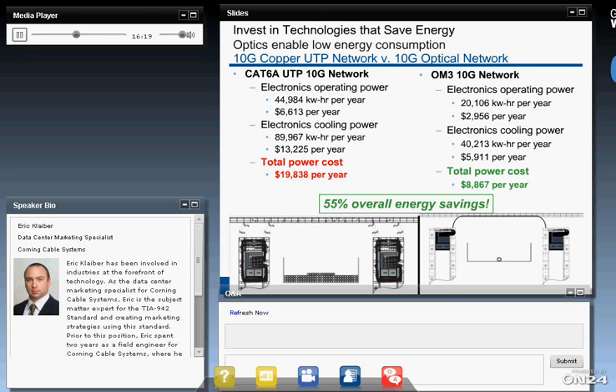You can see just because of that wattage difference per port, there is a substantial savings going from copper to fiber. So copper is more expensive, fiber is less expensive. This is a yearly savings. This isn't just an upfront savings. This is compounding. So the longer you run your data center, the more money you'll save.